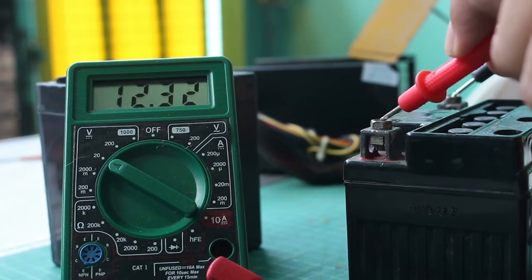Let me give you a little explanation of why that is. A lithium ion battery is a higher voltage to start with than a lead acid battery. Typically, we're nominal around 13.8 volts versus something in the lower 12s for lead acid. But lithium ion holds that voltage much longer. The slope, as energy is consumed, is very low compared to lead acid. So it holds the voltage a much longer period. At the end, the drop off is quite sudden. When you get to the end of usable capacity, the voltage drops, but it's much slower on that.